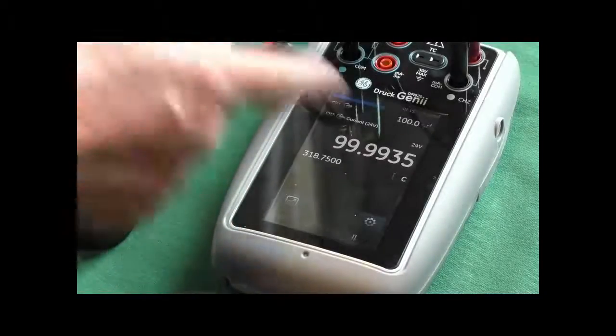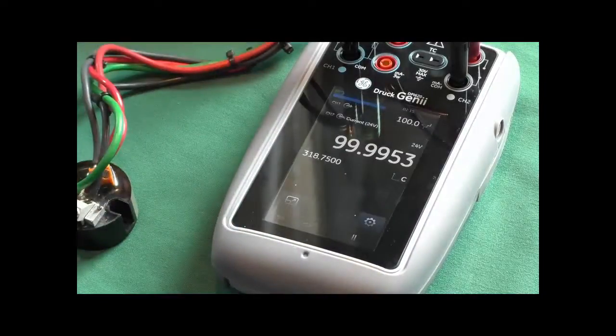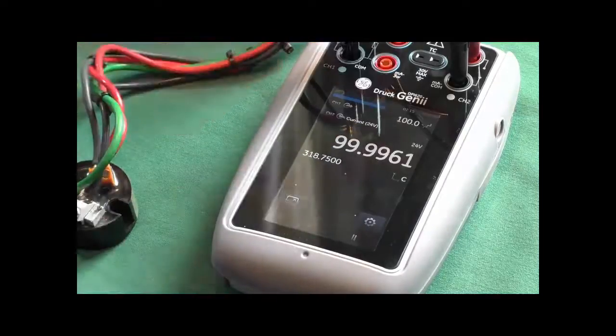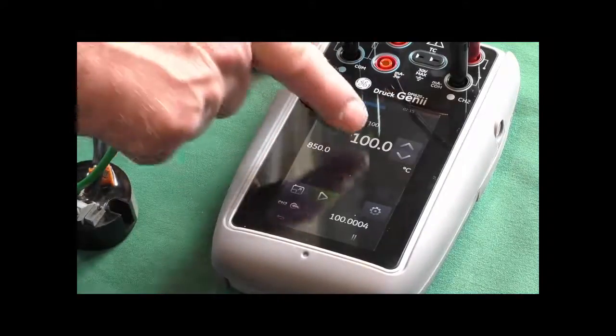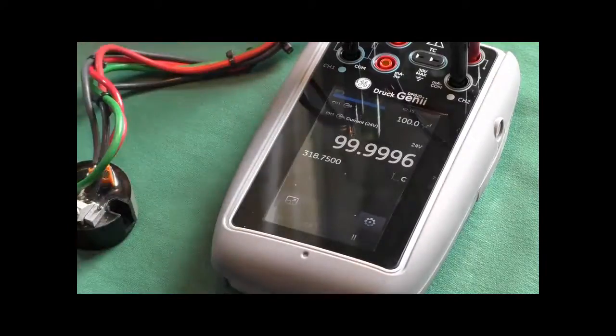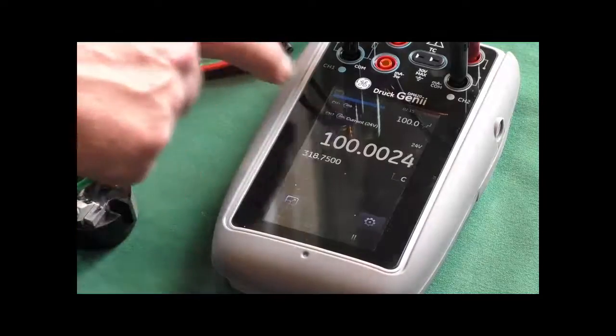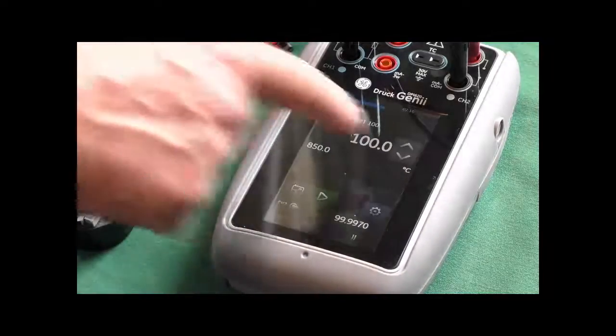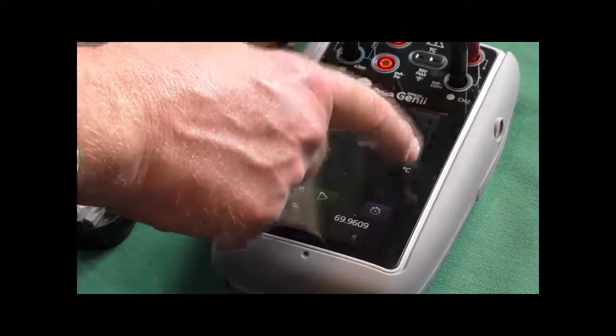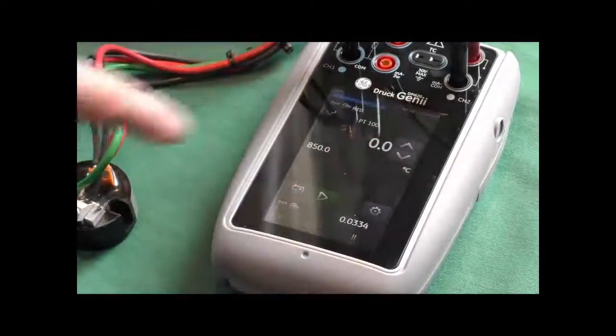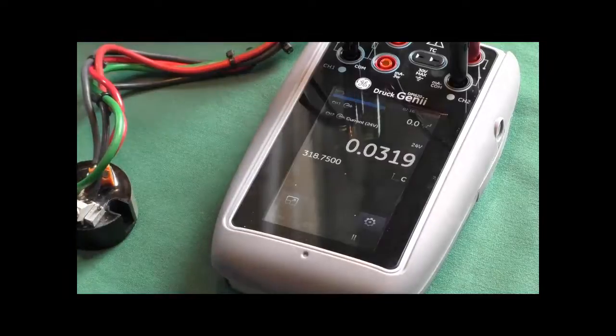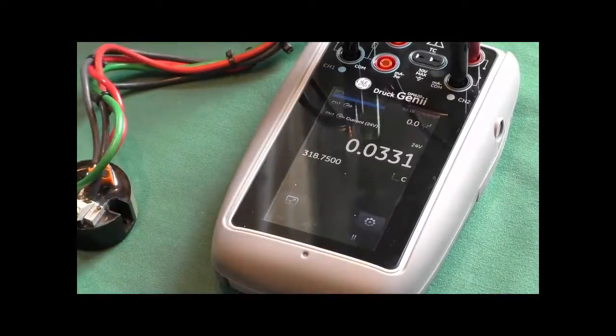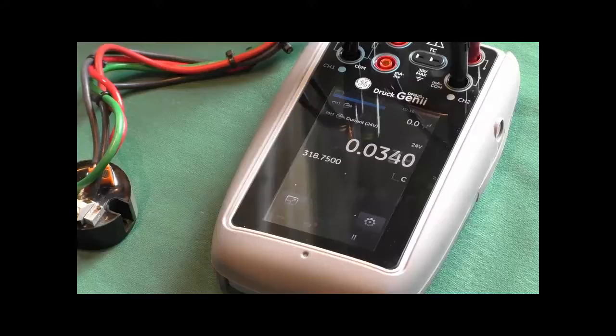And now the scaling, as you see, we are not now reading milliamps on the bottom here. We have got 100 degrees C is what we are simulating. I can open that up, you can see 100 degrees C. And at the bottom we are reading, instead of milliamps, almost 100. And if we go back to the top, and if you remember now, we can nudge this down, come back down to 0 degrees C. And at the bottom, instead of 4 milliamps, we now have approximately 0. So we can see what the error is in actual temperature rather than just milliamps.